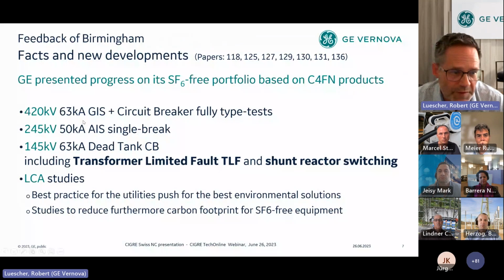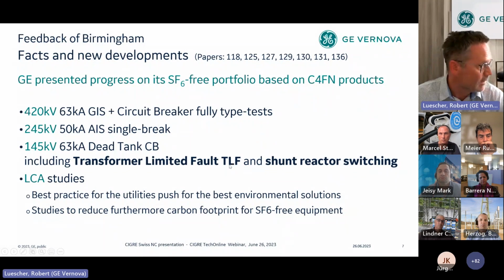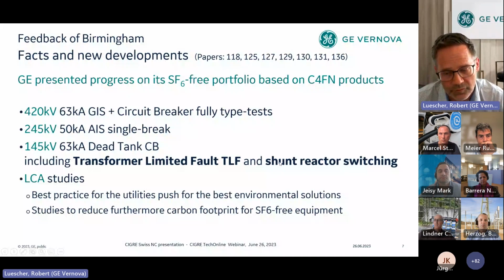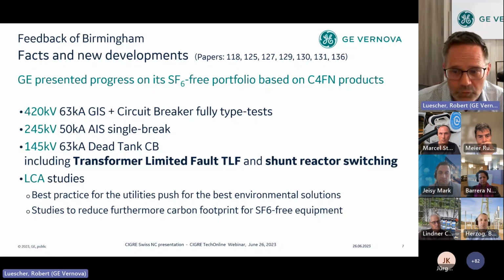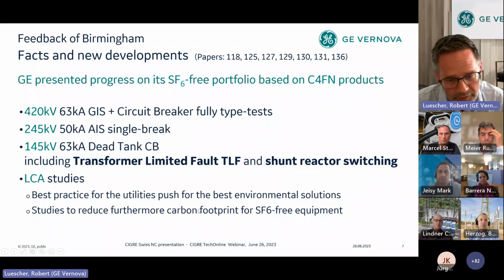From GE's point of view, we have presented a 420 kV circuit breaker with all the type tests. There was a 245 kV AIS single break paper and a 145 kV 63 kiloamp dead tank circuit breaker paper, including the most severe transformer limited fault as defined in IEEE, and also shunt reactor switching - an extended capability of a circuit breaker showing its behavior to synchronize shunt reactors on and off to compensate load in the network. As mentioned, some LCA studies with best practice show how to evaluate the carbon footprint of a solution.